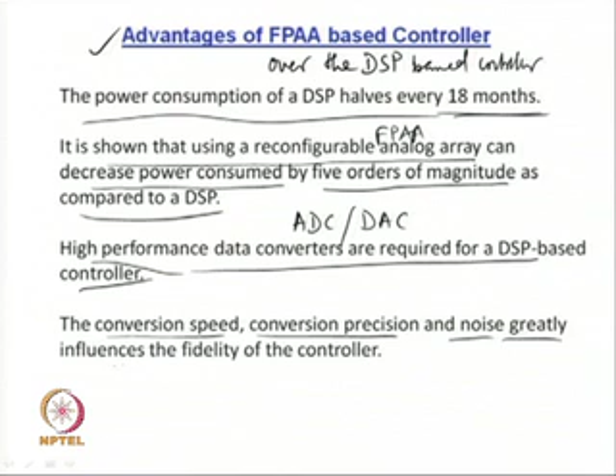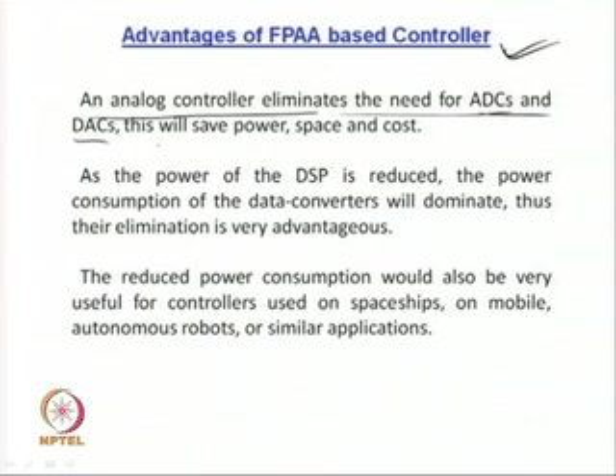High performance data converters, such as analog to digital converters or digital to analog converters, are required for a DSP based PID controller. Those are not required for an FPAA based analog controller. The conversion speed, conversion precision and noise greatly affect the fidelity of the digital controller. That is not so in the case of analog controllers. A further advantage of FPAA based controllers is that the analog controller eliminates the need for converters, which in turn results in saving of power, space and cost. You do not require analog to digital or digital to analog converters. Therefore, you save cost, you save space, and you save power, because power is consumed by the converters.